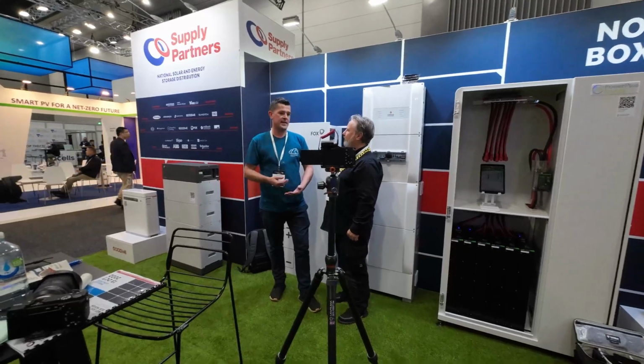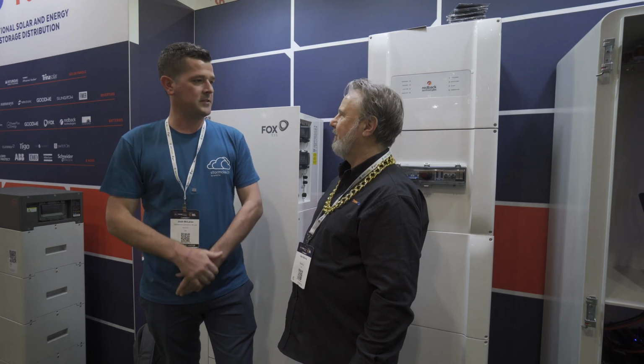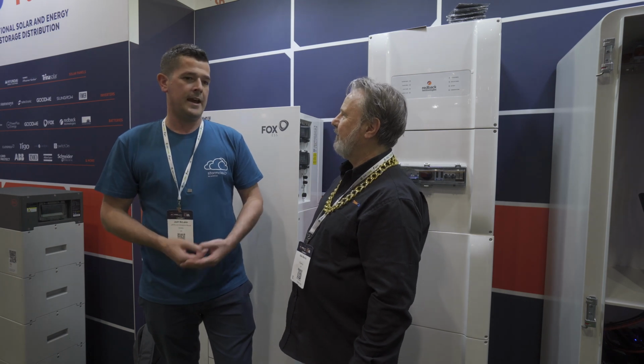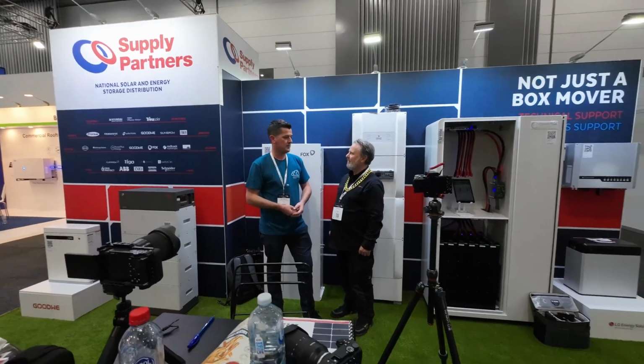Essentially visibility and control to solar, batteries, EV, meters, and we get all the telemetry directly from these devices, generally through Modbus TCP. We integrate with the device, and then we have a little device called a droplet, which I think you're using at the Energy Lab, which will discover those integrated devices once they're on the same network. Once it discovers it, you can commission the device and connect it to the droplet. Once it's connected to the droplet, it's visible on Stormcloud, where we can group it together and send commands.